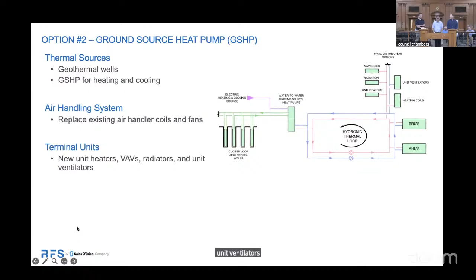That would mean replacing any refrigerant coils in the air handling unit system. So essentially what we do with the air handling unit systems in the previous option is the same here, except that the source is different. The same goes for terminal heating devices. The water temperatures are not nearly as hot as in the boiler system: you're talking about 120 to 130 degree water versus 180 plus or minus. So it requires all the terminal heating devices to be changed. That includes VAV boxes, cabinet unit heaters, propeller unit heaters, unit ventilators, any perimeter fin tube, and stuff like that.